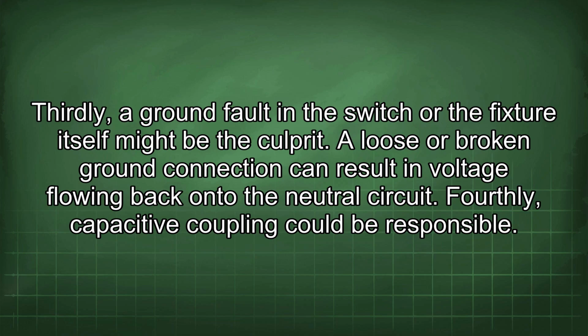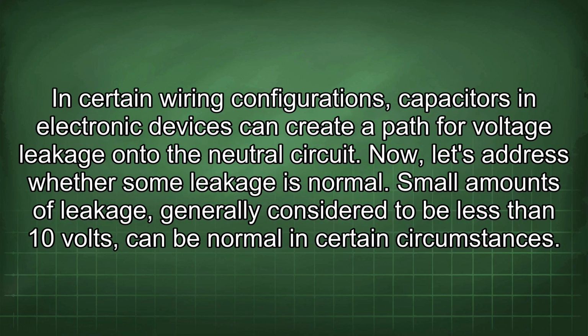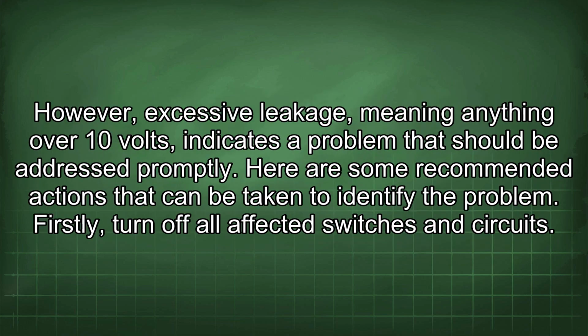Thirdly, a ground fault in the switch or the fixture itself might be the culprit. A loose or broken ground connection can result in voltage flowing back onto the neutral circuit. Fourthly, capacitive coupling could be responsible. In certain wiring configurations, capacitors in electronic devices can create a path for voltage leakage onto the neutral circuit. Now, let's address whether some leakage is normal. Small amounts of leakage, generally considered to be less than 10 volts, can be normal in certain circumstances. However, excessive leakage, meaning anything over 10 volts, indicates a problem that should be addressed promptly.